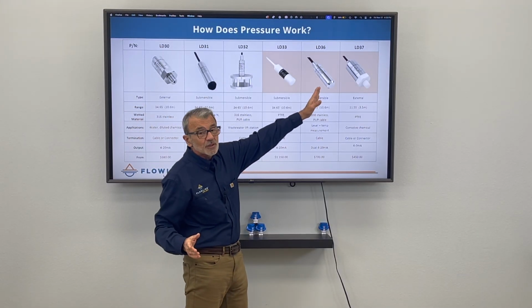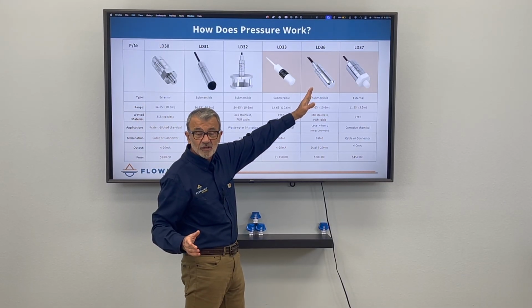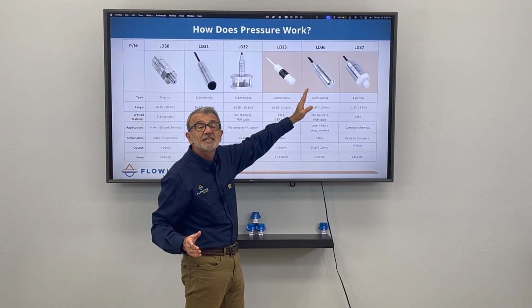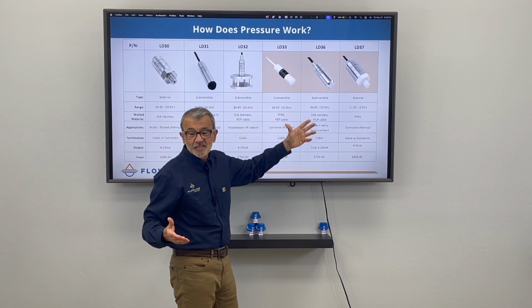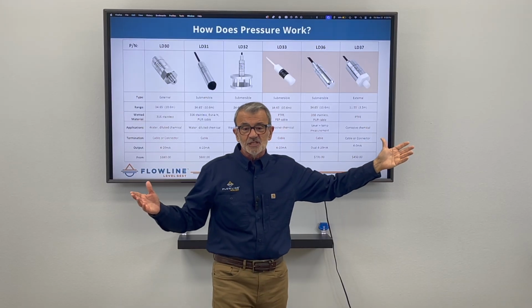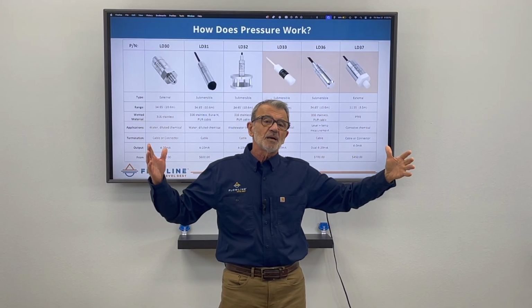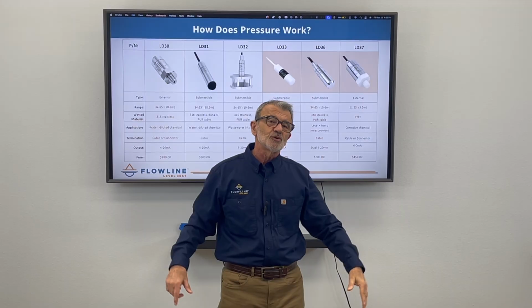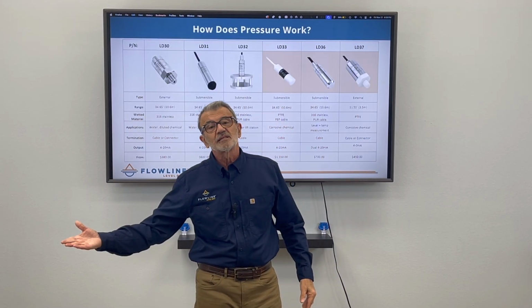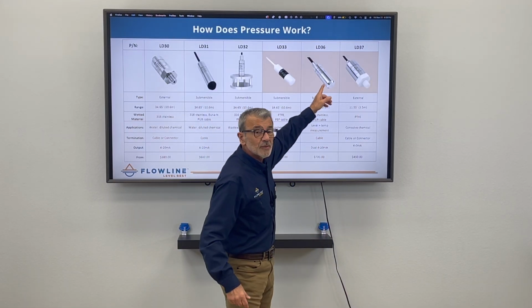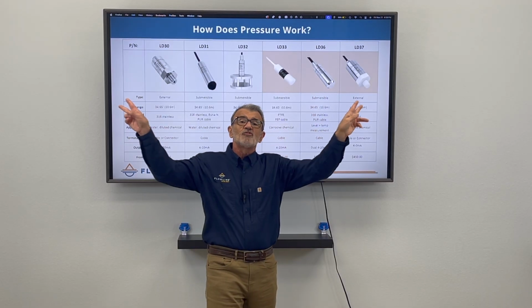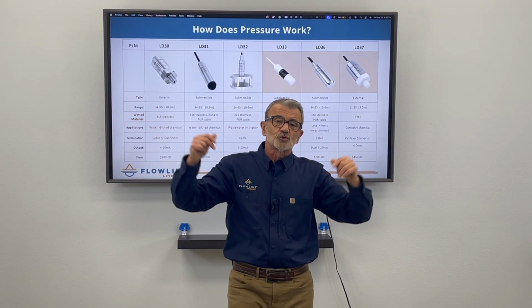Inside this pressure sensor for level, we've also embedded a temperature sensor. It's kind of neat — if you have a chemistry that has to stay at a certain constant temperature and can't get too cold, instead of adding a separate temperature probe, it's all integrated into one, 2-in-1, with two 4 to 20 milliamp outputs for control.